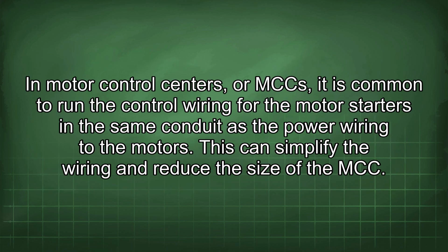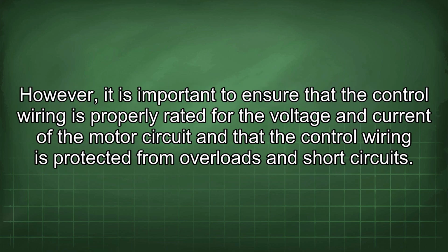In motor control centers, or MCCs, it is common to run the control wiring for the motor starters in the same conduit as the power wiring to the motors. This can simplify the wiring and reduce the size of the MCC. However, it is important to ensure that the control wiring is properly rated for the voltage and current of the motor circuit and that the control wiring is protected from overloads and short circuits.